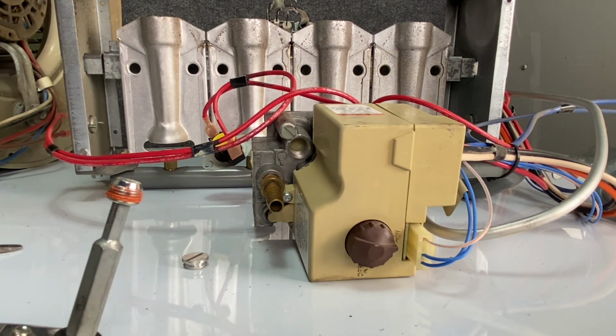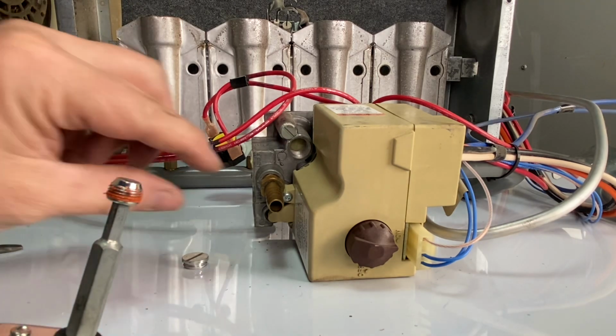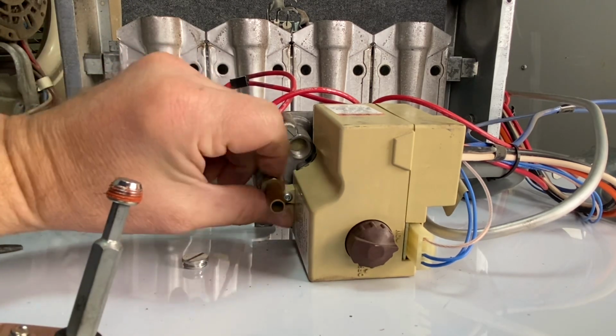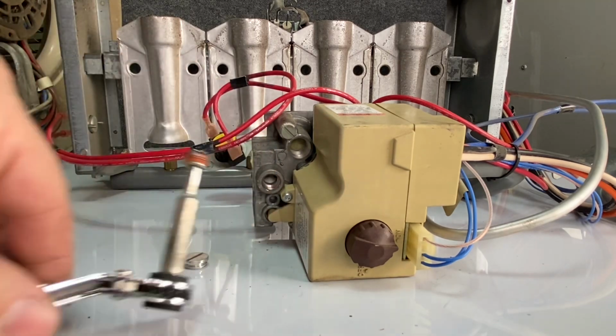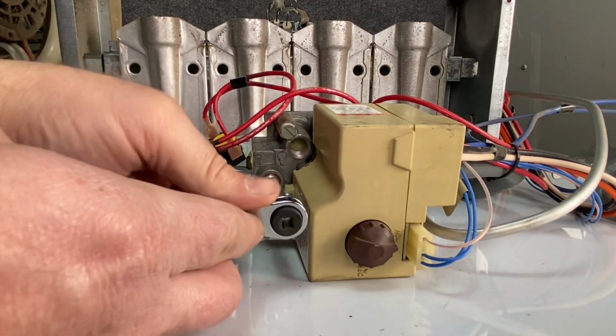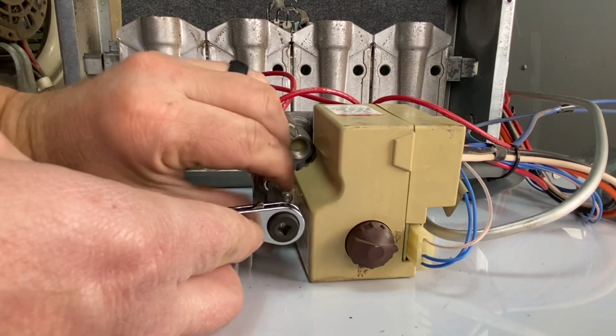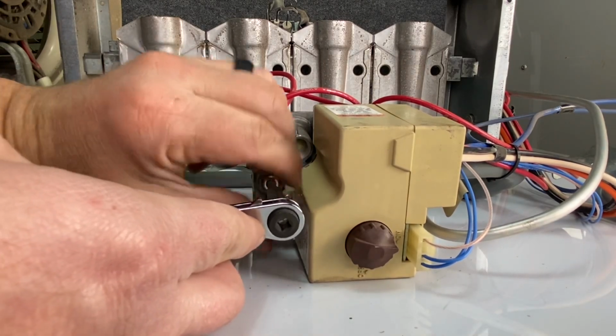Sometimes we'd have a furnace that would be running fine by itself, but if the water heater or stove was running, we wouldn't have enough gas pressure coming into this system. We'd have to remember to shut the gas off, and then we would take this piece back out, and then we would have to put this port back in where it was, otherwise we'd have gas leaking out.